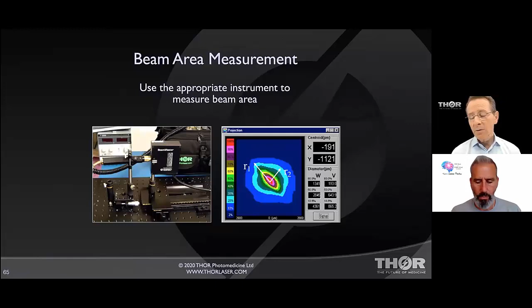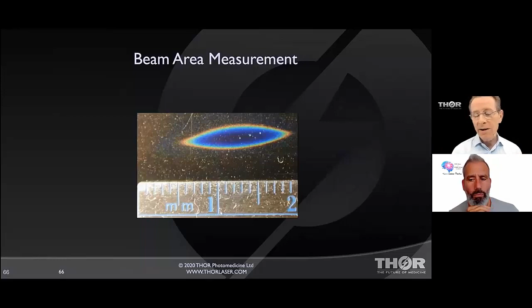I meant to put on another slide here that demonstrates how light coming out of a light guide from a dentist's photobiomodulation device comes mostly down the middle of the fiber of the bundle of fibers, and a lot of people assume that the size of a laser beam or light source is the size of the aperture, and it's not. Very often the source is much smaller than the aperture, particularly when it comes to lasers. And that's not the only problem. Not using the right instrument is a problem.